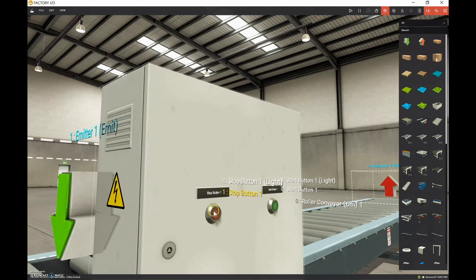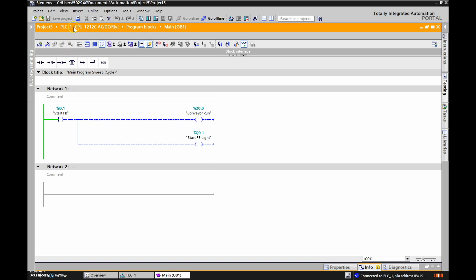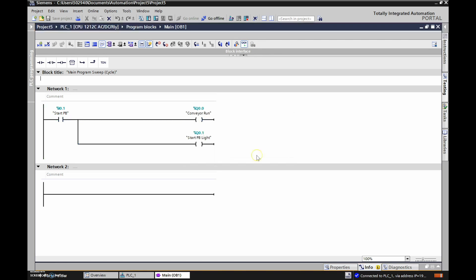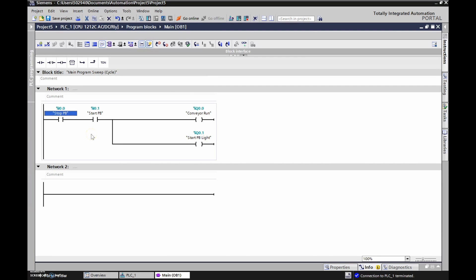Now that we've created everything in Factory IO to accommodate the new stop and start push buttons, let's go over to our PLC program. I'm using Siemens TIA Portal but use whatever you have — Allen Bradley, TwidoSuite, or any other PLC. We're going to take this offline and make some changes. We have a start push button; in series with that we need to put a stop push button. We're going to use an XIC — a normally open contact — and drop it in. Based on what we just did in Factory IO, that input is 0.0. Hit Enter. Now right click and rename the tag: input 0.0 is our stop push button.